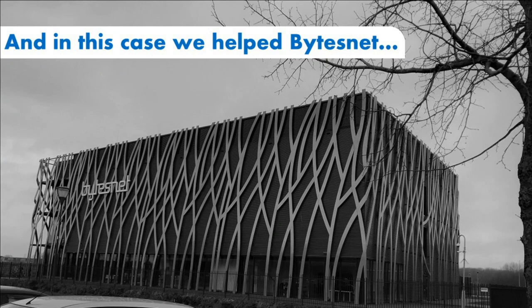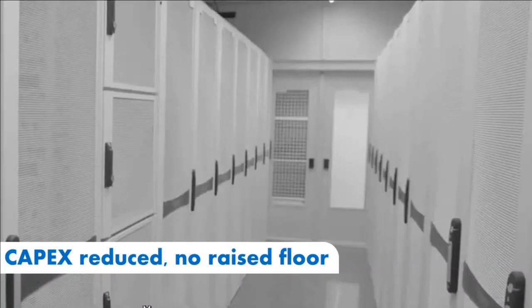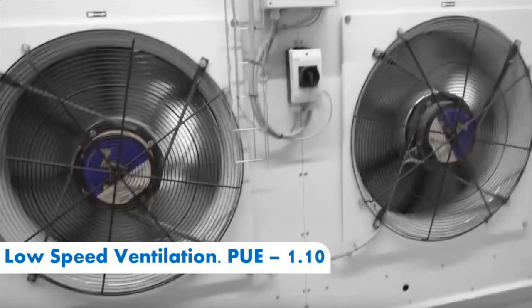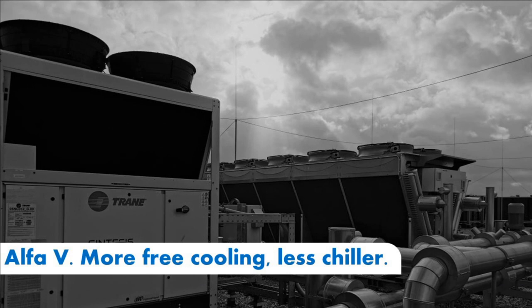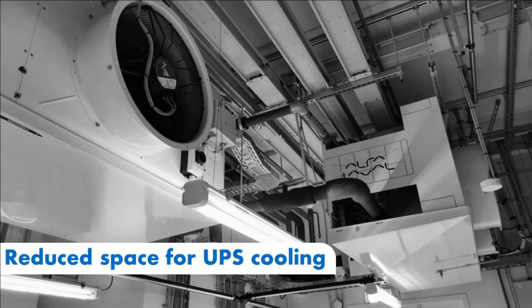And the next client in the Netherlands already had a commercial data center with CRAC units in Rotterdam and was building the next one in Groningen. And he chose the low-speed ventilation solution with lower PUE, cheaper general capex, and no raised floor. Part of the low-speed ventilation is visible in the background. Low-speed ventilation fans rotate at low speed and minimal power consumption. The system is based on dry coolers for free cooling and a series-connected air-cooled chiller with a calculated PUE of 1.10. A high switching point for free cooling allows 75% of the time in a year to work without a chiller. The cooling of the room with UPS also occurs using low-speed ventilation, which is suspended from the ceiling and significantly reduces the used area.